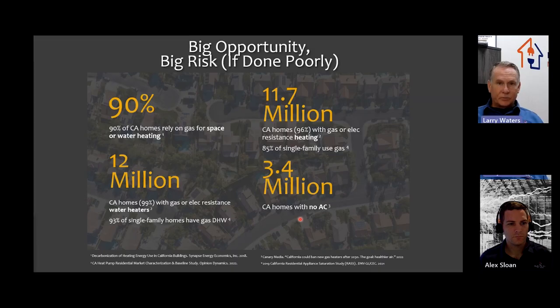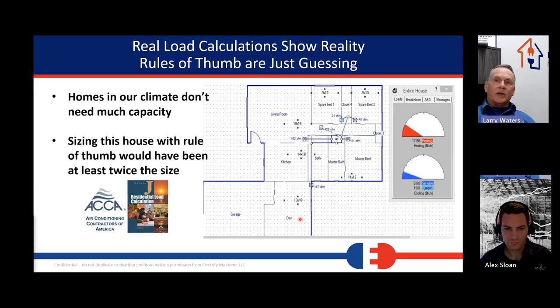So I think SMUD did some research recently. I don't think that slide's in here, but SMUD did some research recently, and they found that by putting inverter systems in, we overall reduce the amount of energy needed. By putting heat pumps that are non-inverter in, we were increasing the amount of energy. So if just everybody took out every single stage air conditioner in California and put in an inverter, we wouldn't have to worry about the grid because we'd be using less energy than we're currently using, even with 3.4 million new houses online. So we need to do this right, folks. Okay, I've preached there. Okay, so real load calculations. So really, okay, real load calculations are not rules of thumb.